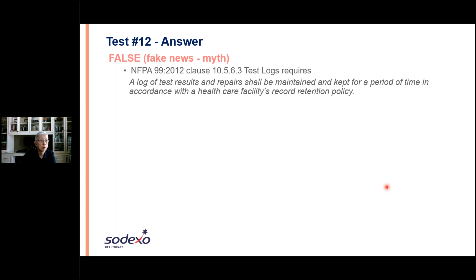Okay, it's false. Good for those who remember that actually NFPA 99, which as I mentioned before has been adopted officially by CMS and therefore Joint Commission, DNV, etc., says there is a log of test results that you need to maintain. However, it has in its appendix a note, this clarification, that there are several approaches to documentation. At the end of it, it says you can thereby minimize technicians' time in recording the values of each measurement taken, because the only values that need to be recorded are the failure or deviation from the requirements of the chapter that was detected when the corrective repair was undertaken. In other words, this is the so-called exception reporting.